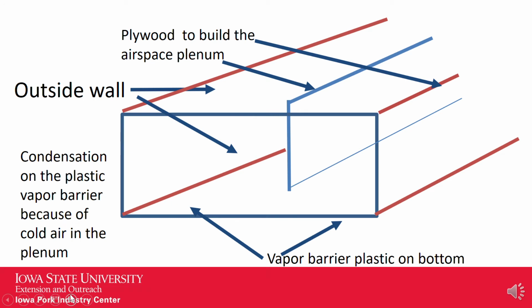This is a picture of a plenum. The idea is to bring cold, fresh outside air in and run it through a box along the ceiling, allowing the outside air to warm up as it blows by the warm inside air. The air can then be dumped into a heated room to be pushed back into the room with positive pressure through what I call engineered inlets.